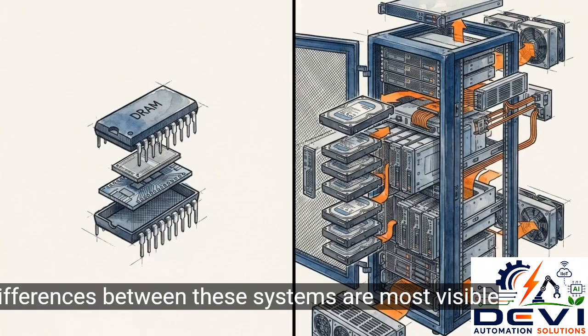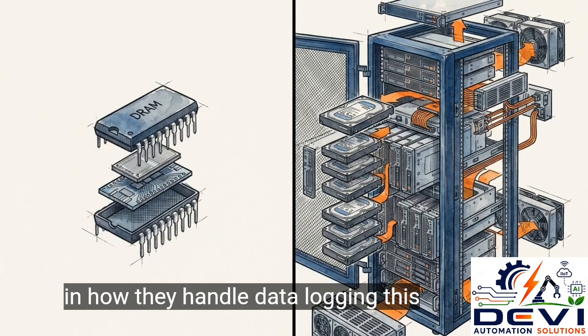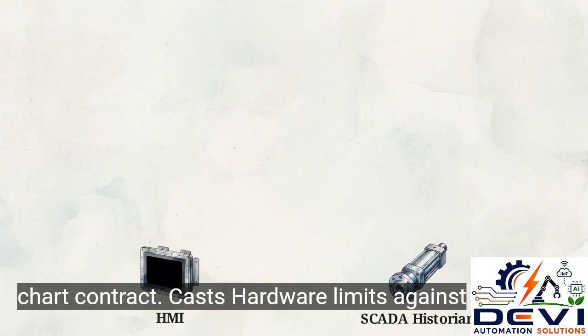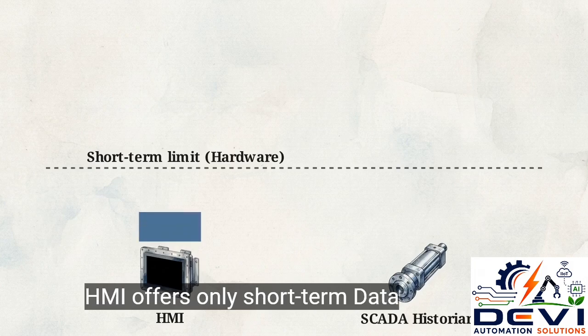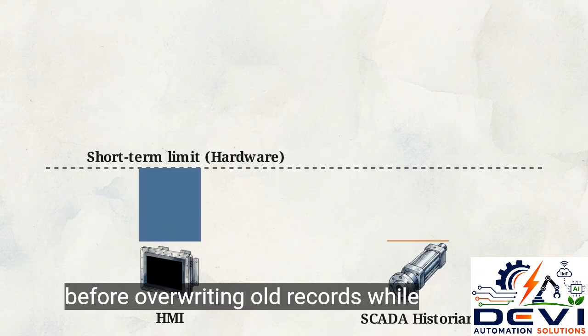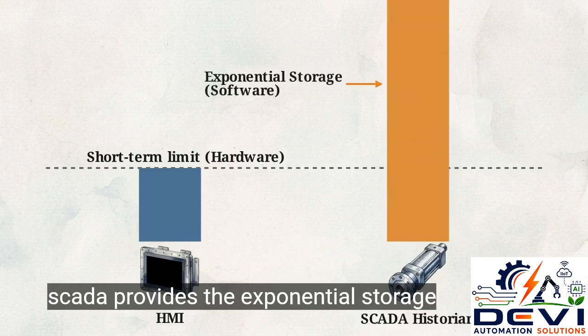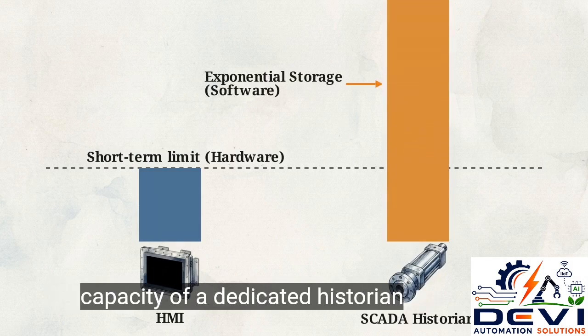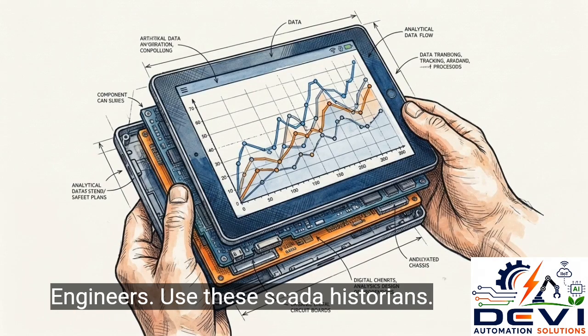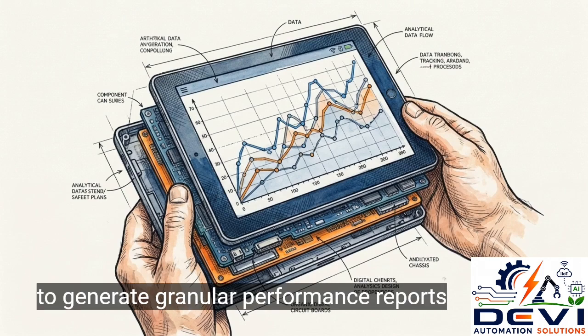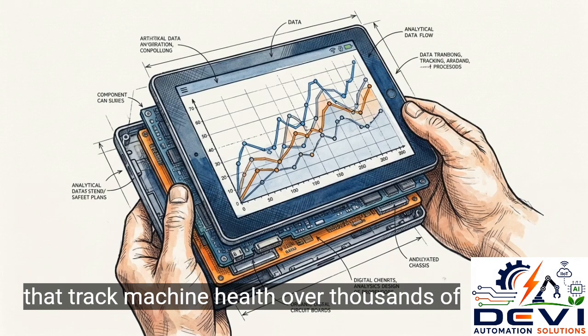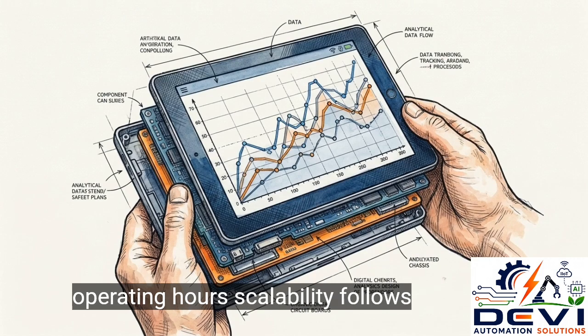The practical differences between these systems are most visible in how they handle data logging. This chart contrasts hardware limits against software scalability. An HMI offers only short-term data before overwriting old records, while SCADA provides the exponential storage capacity of a dedicated historian. Engineers use these SCADA historians to generate granular performance reports that track machine health over thousands of operating hours.